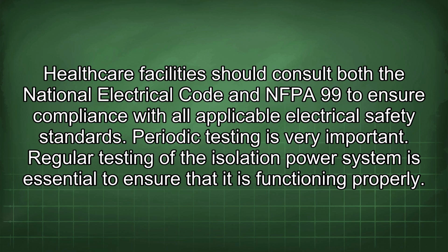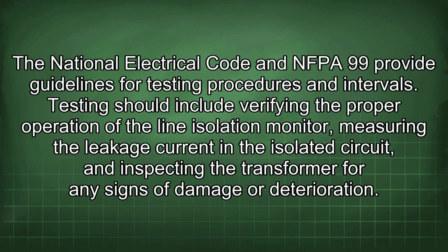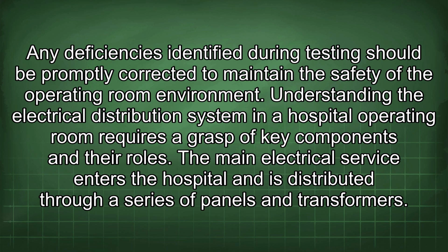safety standards. Periodic testing is very important. Regular testing of the isolation power system is essential to ensure that it is functioning properly. The National Electrical Code and NFPA 99 provide guidelines for testing procedures and intervals. Testing should include verifying the proper operation of the line isolation monitor, measuring the leakage current in the isolated circuit, and inspecting the transformer for any signs of damage or deterioration. Any deficiencies identified during testing should be promptly corrected to maintain the safety of the operating room environment.